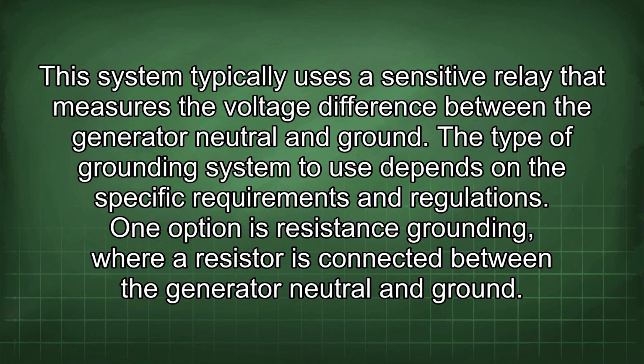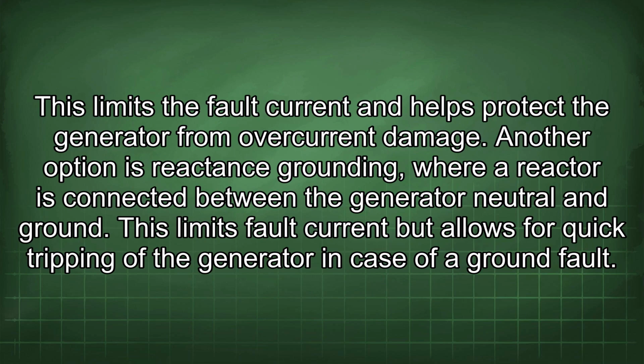The type of grounding system to use depends on the specific requirements and regulations. One option is resistance grounding, where a resistor is connected between the generator neutral and ground. This limits the fault current and helps protect the generator from overcurrent damage. Another option is reactance grounding, where a reactor is connected between the generator neutral and ground. This limits fault current but allows for quick tripping of the generator in case of a ground fault.